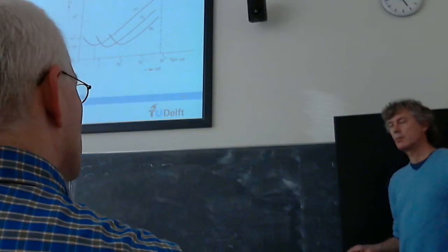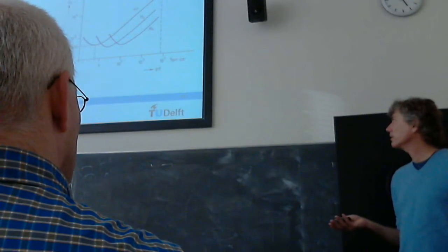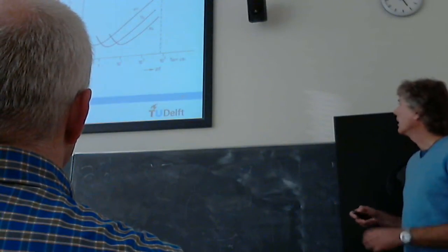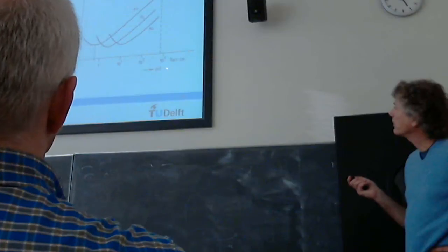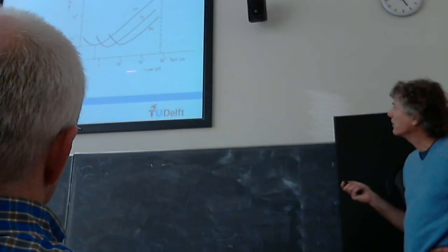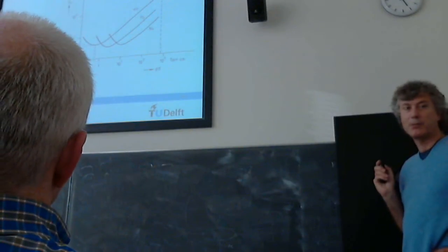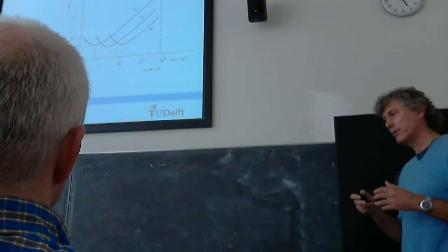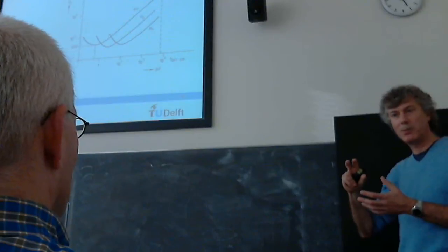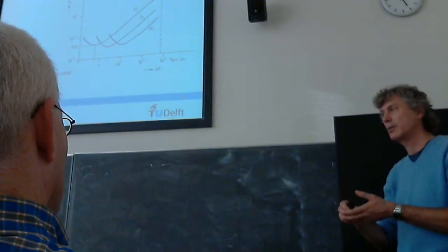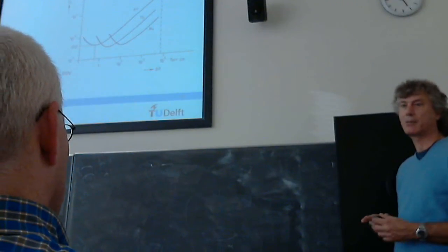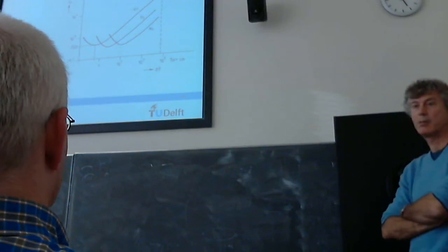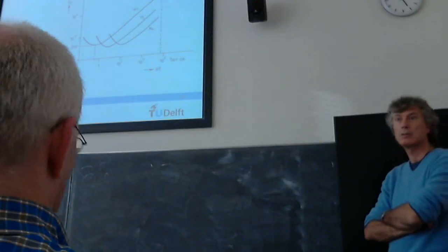If we assume, again, 1 atmosphere pressure, we can look for different sizes of cavities, what is the breakdown voltage? And then we can calculate from the voltage we apply on the cable back to the voltage across the cavity, whether this voltage would lead to a breakdown in the cavity. This is how often people use the Paschen curve, Paschen's law.